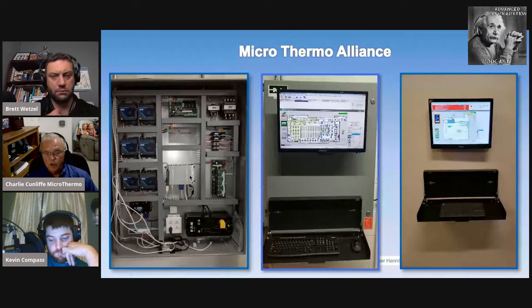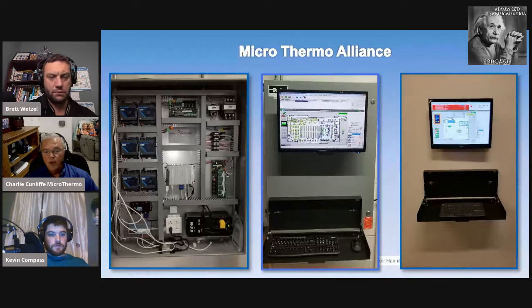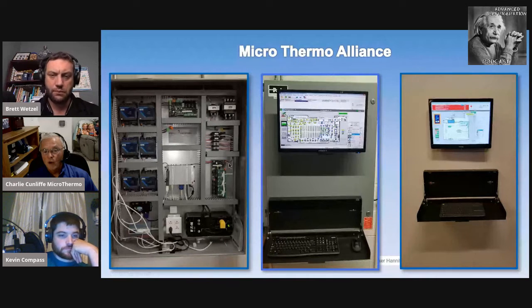So here's the Windows device, the HMI. Here's the USB adapter, here's my black and white wire. It starts right from there - the very first thing I hit is the alarm node. Now you see there's no wire coming out of here, so that you can't make the mistake of starting your network from here. So we start over to here, and then we pick up these nodes, and then we go out to the building from there.